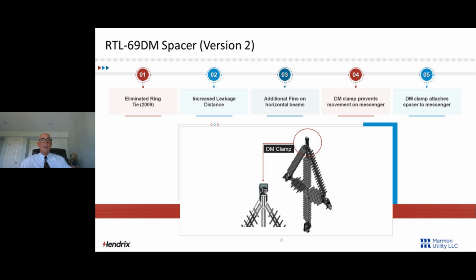In 2009, we said, hey, it's time to get rid of the ring tie and make it ring tie less, like our other voltages. We wanted to increase the leakage distance because we wanted to get into areas that were a bit more contaminated. We wanted to put more fins on the horizontal beams, and we wanted to put that good old DM clamp on the messenger. You see the circle around here. When you hook that on the messenger, it can't roll backwards or forwards. So now we have more positive staying power of that spacer where it belongs, rather than having the ability to move. So that was the second version.